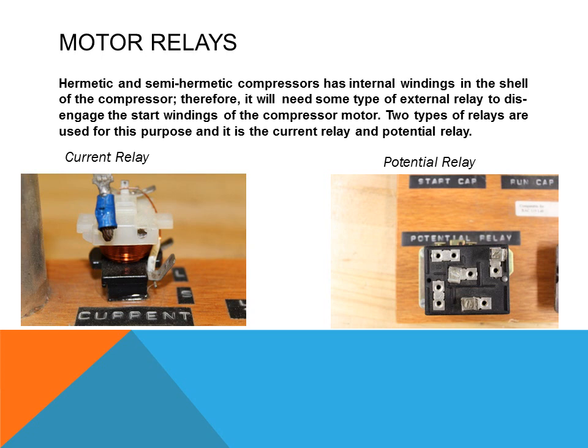Other types of relays you may find relate to compressors. Hermetic or semi-hermetic compressors have internal windings inside the shell, so an external relay is needed to disengage the start windings. Two types are used: a current relay for very small fractional horsepower motors such as those in domestic refrigeration or dehumidifiers, and a potential relay for larger compressors over one horsepower.